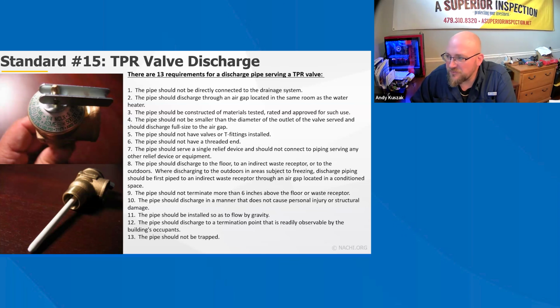Temperature relief valves should be installed within the top 6 inches of the tank. The valve should be set to open at a maximum temperature of 210 degrees Fahrenheit. Discharge from a relief valve should be immediately investigated. A discharge indicates that something is wrong with the system. The discharge point should be conspicuous. The termination of a relief valve discharge pipe should always be visible and conspicuous.